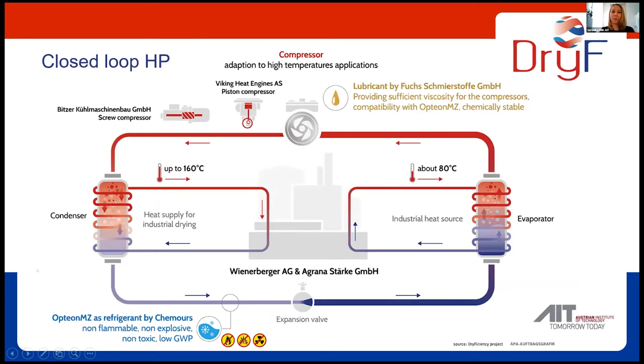This is an illustration of the closed loop heat pump and the most important aspects that we were working on in that project. I want to start with the industrial waste heat source, and I really like the framing that Josephine introduced at the beginning. This is our source for the circular energy that we are using. Waste heat has temperatures around 80 degrees C, and it is used to evaporate the refrigerant. The refrigerant is compressed either in a screw compressor or a piston compressor. This is also where we use the lubricant. The lubricant has to be sufficiently viscous for the operation of the compressors, and it also has to be compatible with the refrigerant.